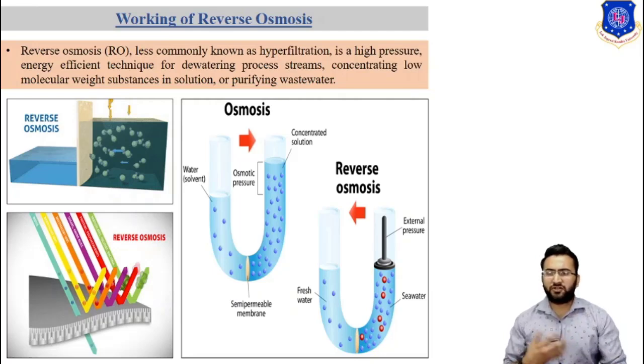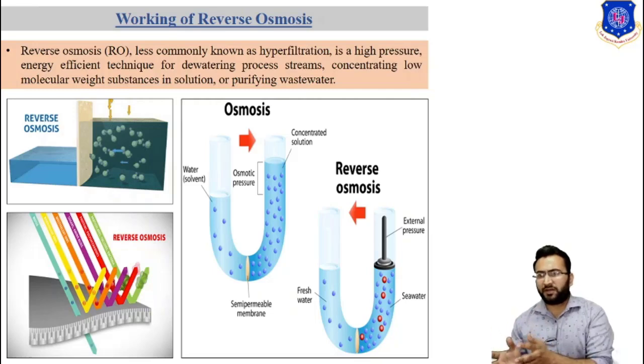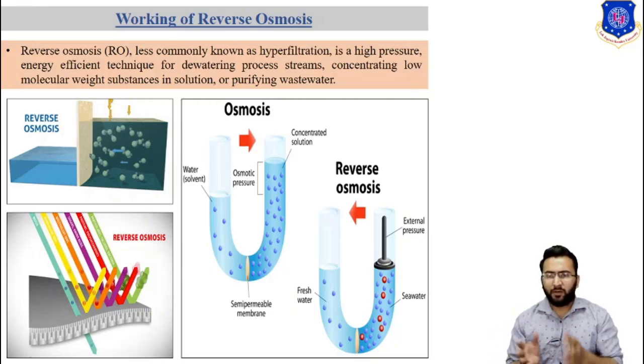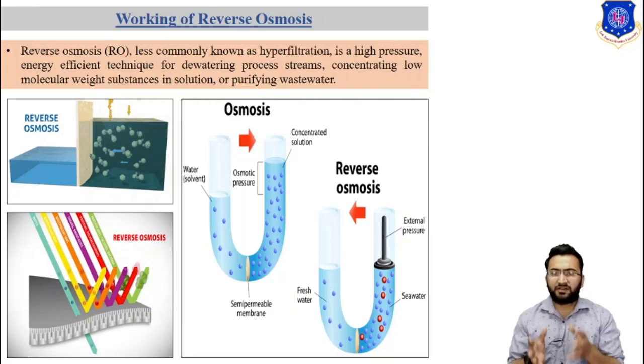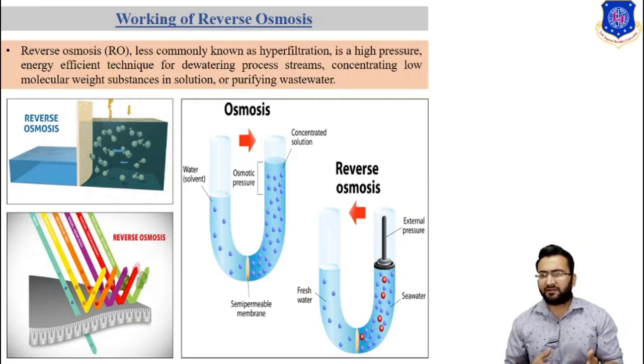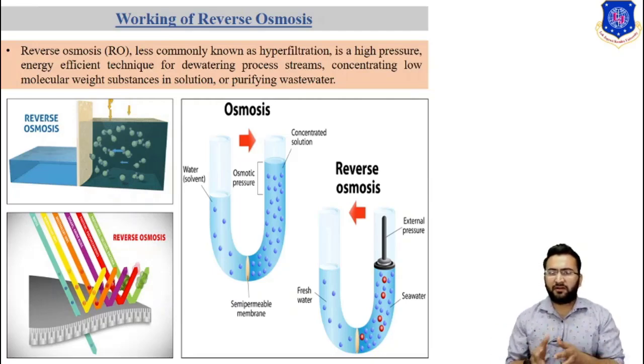To reverse the natural process of osmosis, it is required to overcome the osmotic pressure equilibrium across the membrane, because the flow is naturally from dilute to concentrate. We want pure water, so we must increase the salt content in the cell. To do this, we increase the pressure on the salty side of the membrane and force the water across. The amount of pressure is determined by the salt concentration. As we force water out, the salt concentration increases, requiring even greater pressure to get more pure water.